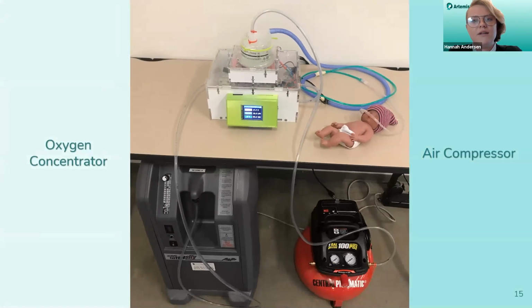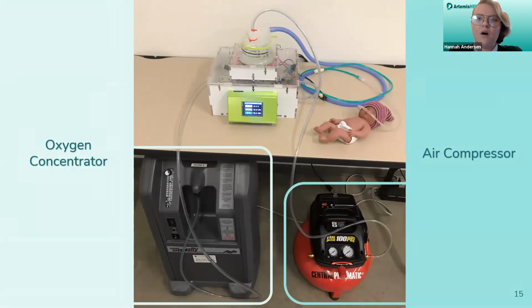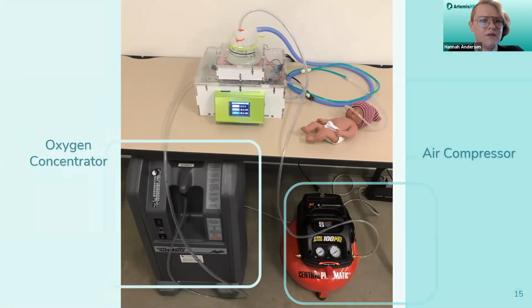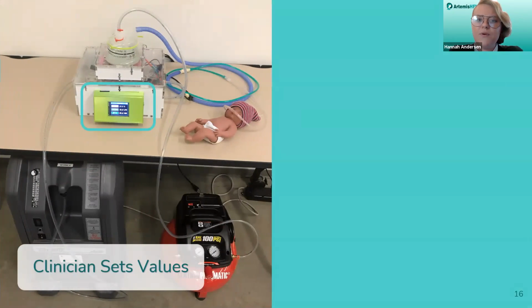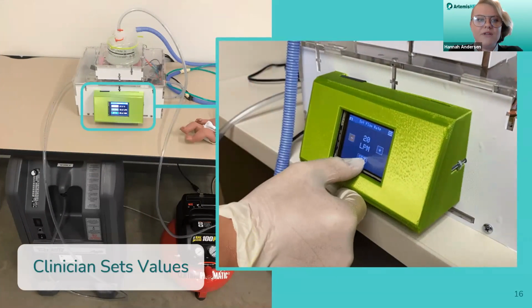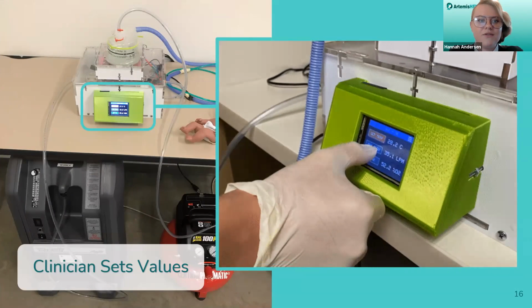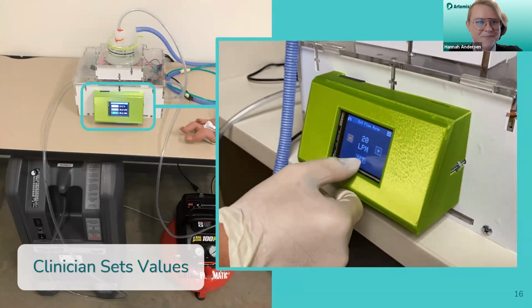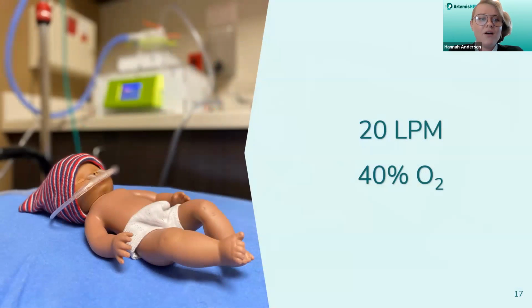So here we're showing it attached to an air compressor and also an oxygen concentrator, which is really commonly used as an oxygen source in low-income settings. So second, the clinician is able to input the values for the prescribed therapy on the touchscreen, which sends information to the controller to provide the desired therapy. So for example, let's say John is prescribed 20 liters per minute with an oxygen concentration of 40%. And what this does is it expels old recycled air from his lungs and it increases his blood oxygen levels.